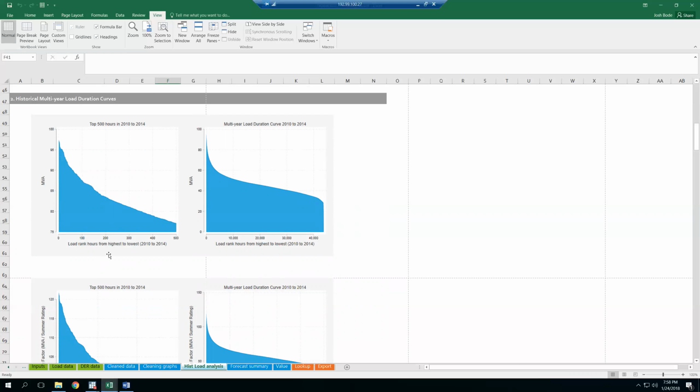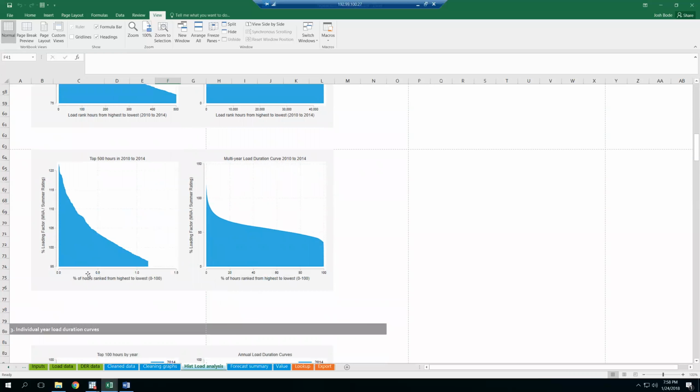You can exceed it for some hours because it has more to do with having a contingency in tandem for it to matter. But if you're exceeding it too many hours, you're exposing yourself to too much risk. So we're looking at load duration curves as the key trigger for the results, in particular whether or not that load duration curve amount is above a certain threshold for a prolonged period of time.